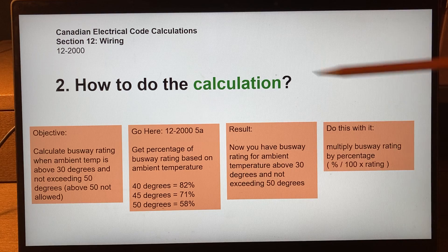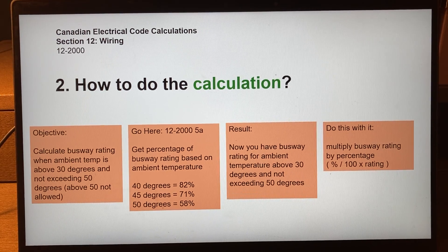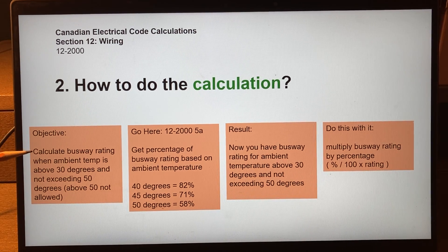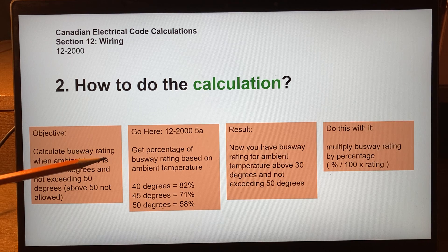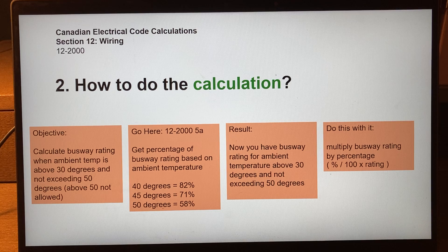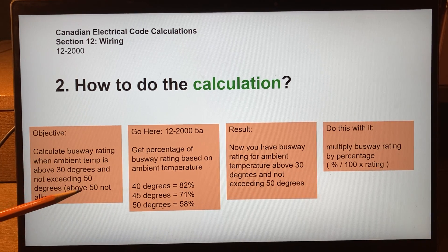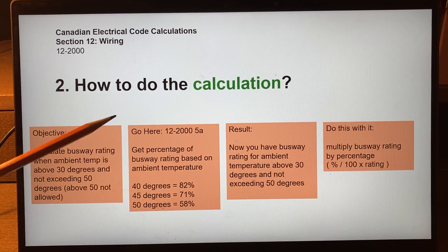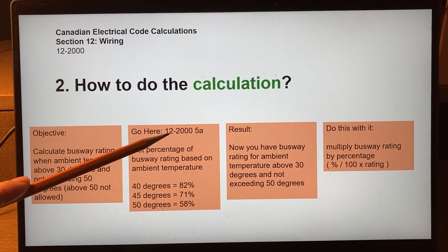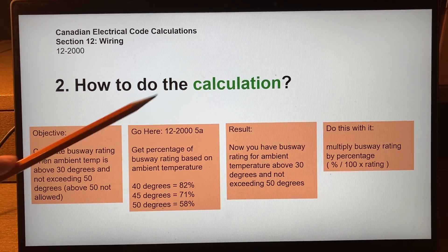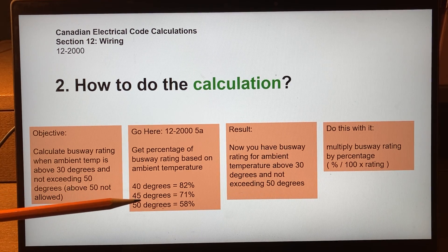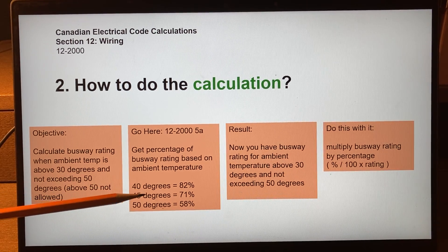There is a calculation in rule 12-2000. The objective is to calculate the busway rating when the ambient temperature is between 30 and 50 degrees Celsius, because above 50 degrees is not allowed. The calculation is found in rule 12-2005(a). You look at sub-rule 5 and, although it is written with a lot of words, what it basically tells you is the de-rating percentages based on temperature.